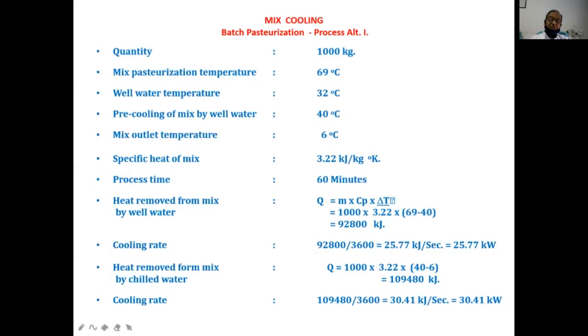So here you can see it is 1000 kg, 3.22, 69 minus 40, which is 92,800 kilojoule, the load on the cooling tower or the well water, my dear friend. It is not the total load because we have gone only up to 40 degrees. If you calculate in kilowatt, it's 25.77 kilowatt. We get the cooling rate, or cooling load, for the well water or the cooling tower.